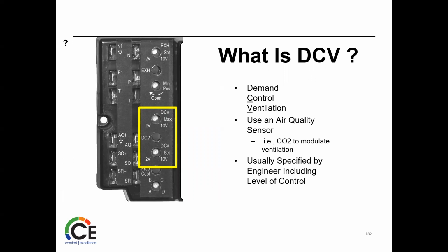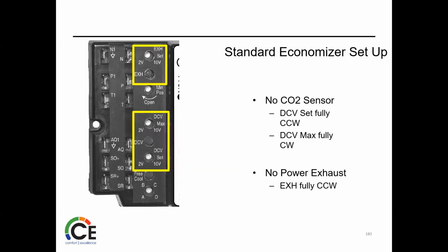Demand control ventilation, or DCV as the abbreviation, is there if we need to use an air quality sensor, CO2, to modulate. That's when we're getting into that, where if we're trying to monitor for CO2 or whatever the engineer or the building needs, that's what these are set up for. Standard economizer setup, you're not going to have a CO2 sensor. So DCV is set fully counterclockwise.